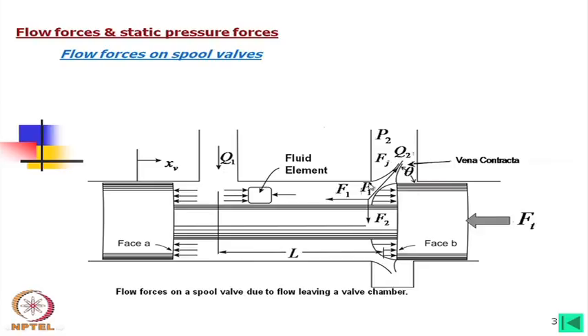This angle is called the jet angle. If we think of the area, it is rectangular for a full opening — we consider pi times d, where d is the spool land diameter. The flow goes out like an umbrella at angle theta, the jet angle. Within that area there is a smaller area called the vena contracta. We must calculate the vena contracta area to find the flow rate and pressure drop.